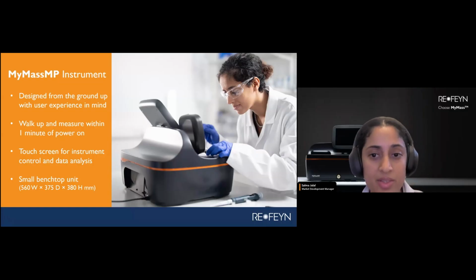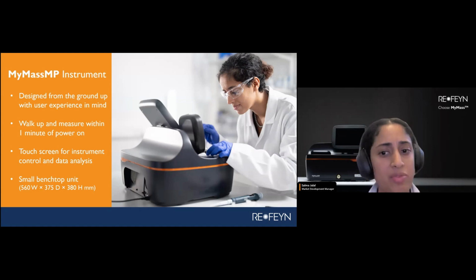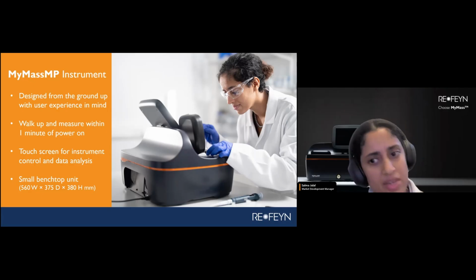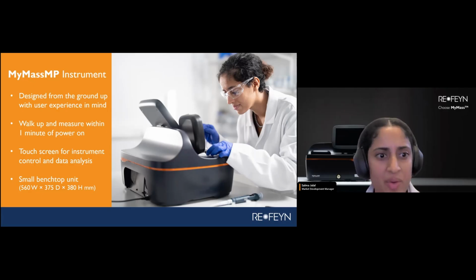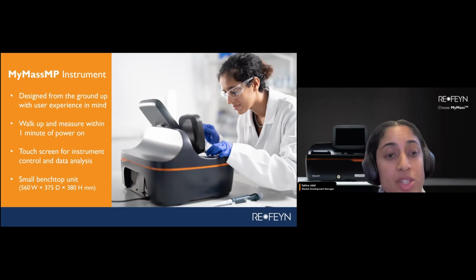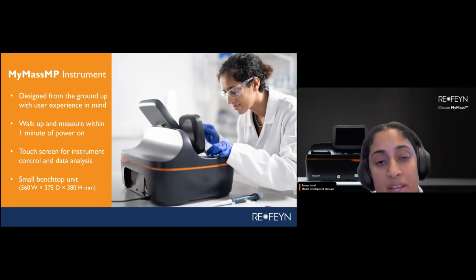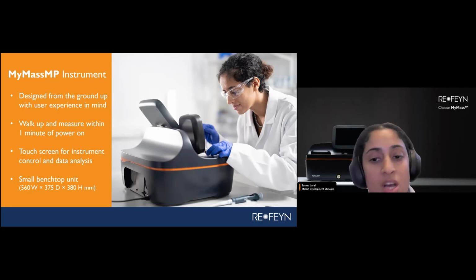MyMass MP is an instrument that we designed from the ground up with the user experience in mind. So checking samples can easily fit into your everyday workflows instead of you having to work your sample checking around and making time for that in separate ways. So one feature that achieves this is the fact that you have no warm-up time with this instrument. So you can walk up, turn on the instrument, and take a measurement within a minute.